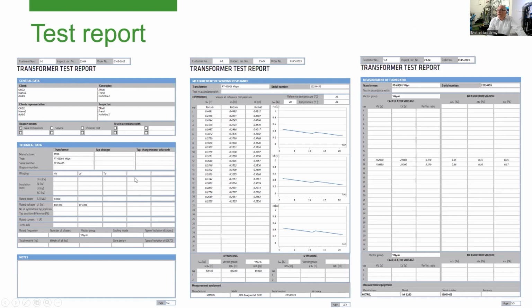Additional comments can be added, configuration basic is added, and so on. The next page includes the data of the winding resistance measurements, all in numerical and graphical form, of the primary side. On the secondary side, usually only numerical, and it includes this report and also a report for the transformation ratio measurement, which cannot be done with this instrument, but with the digital transformer analyzer.